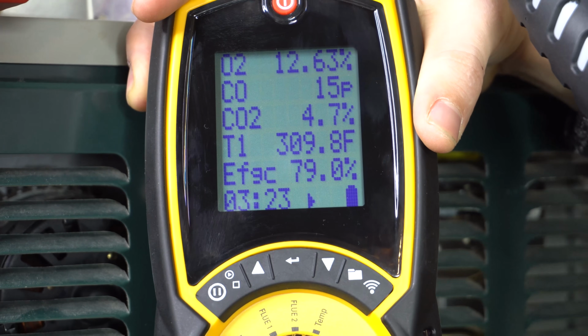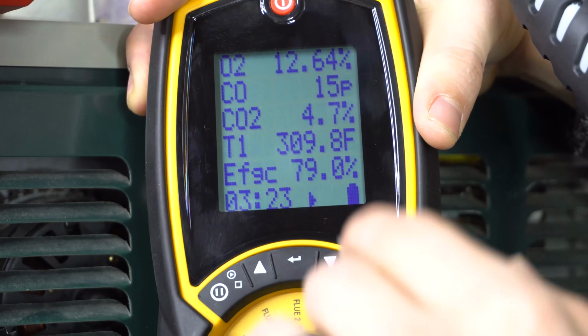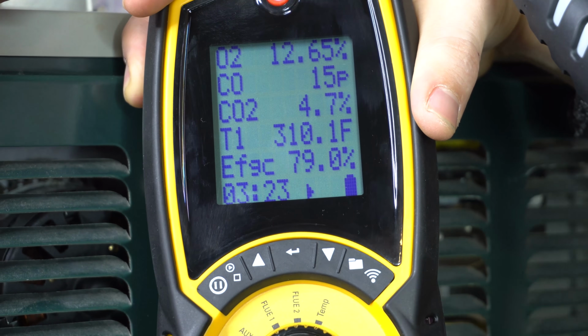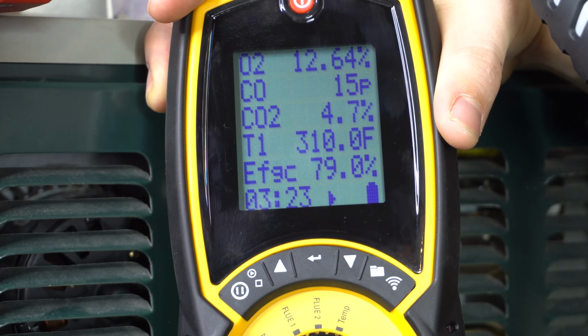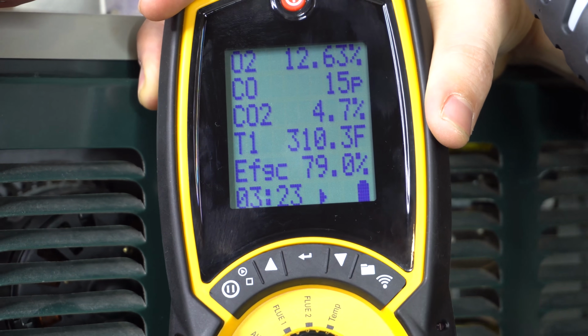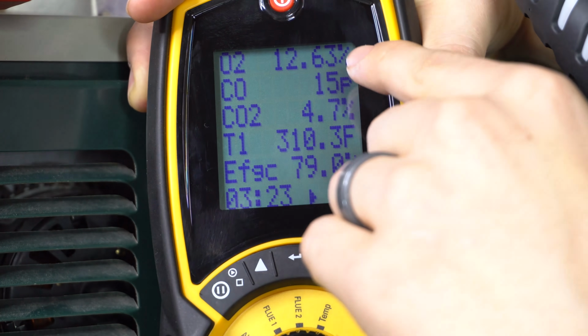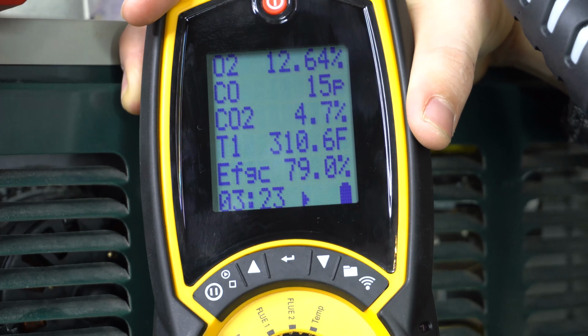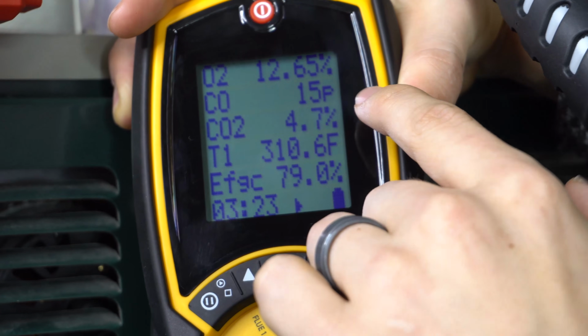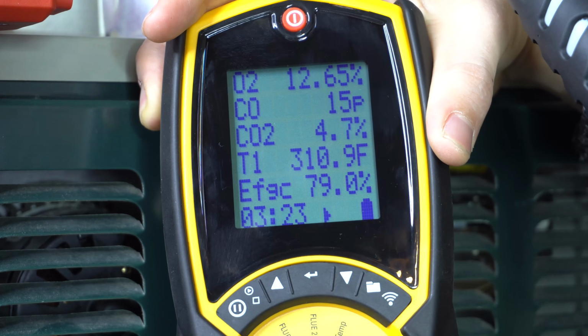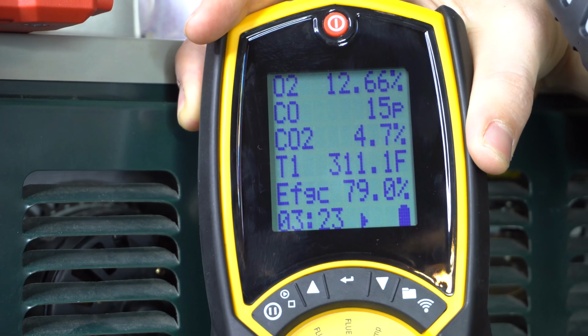After about 2 minutes, the numbers have stabilized. My oxygen is at about 12.6%, and typically on most inspections and checkups that I do, the oxygen is between 8 to 12%. It's a little bit on the high side, but I'm not worried about it, especially since my carbon monoxide is at 15 parts per million. If the carbon monoxide is below 50 parts per million, you're pretty much good.